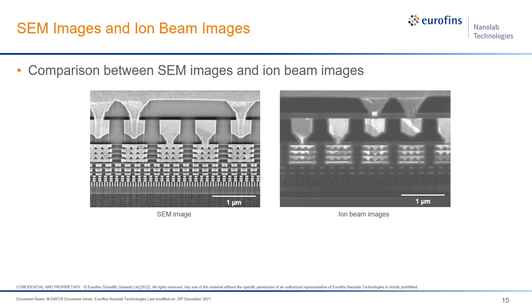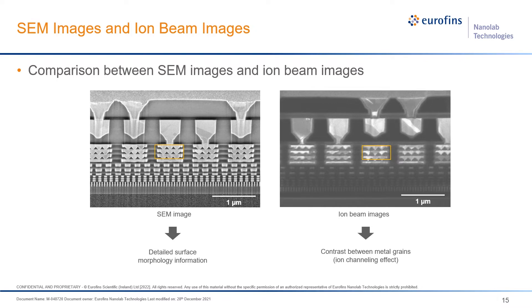Sample surfaces and cross-sections can be imaged by both electron beam and ion beam. SEM images give high-resolution structural information. However, due to the high energy of the ion beam, when a metal surface is exposed, different grain orientations interact differently with the gallium ions — this is called the ion channeling effect. As a result, contrast between grains is much more obvious in ion beam images, revealing metal grain information. Ion beam images are not as sharp as SEM images and cause surface damage due to gallium ion bombardment.